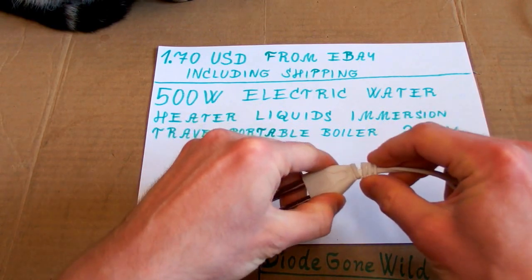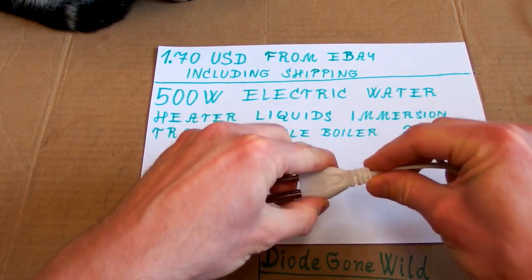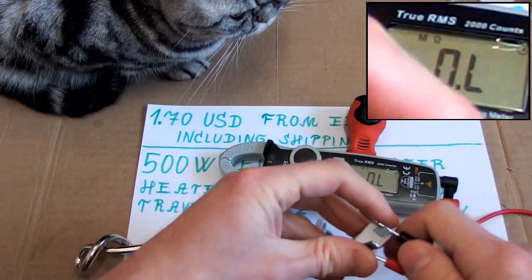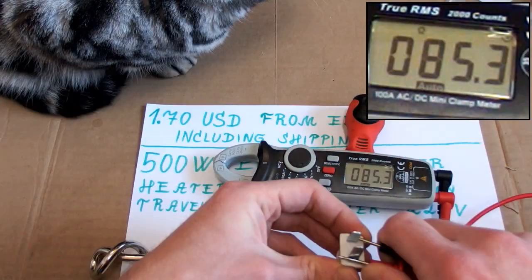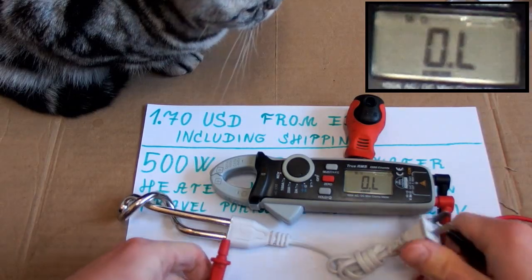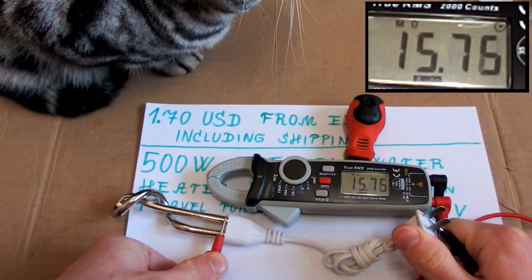And so the resistance of the heating element is about 85 ohms. Now is it isolated from this metal? 15 mega ohms.